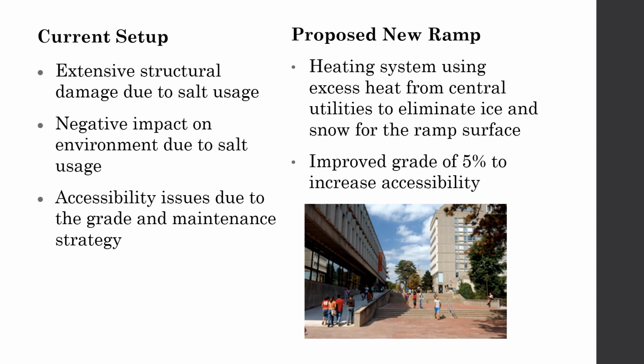Our proposed new ramp design will address and fix all of these issues. The implementation of a hydronic heating system will prevent the buildup of ice and snow, and the ramp will be rebuilt with a proper grade of 5%. The system will draw excess and unused low-grade heat from the central utilities heat stack to heat up the propylene glycol and water mixture. This mixture will be run through pipes underground in the pre-existing tunnels to the library ramp, where it will be used to eliminate the ice and snow buildup on the surface of the ramp.